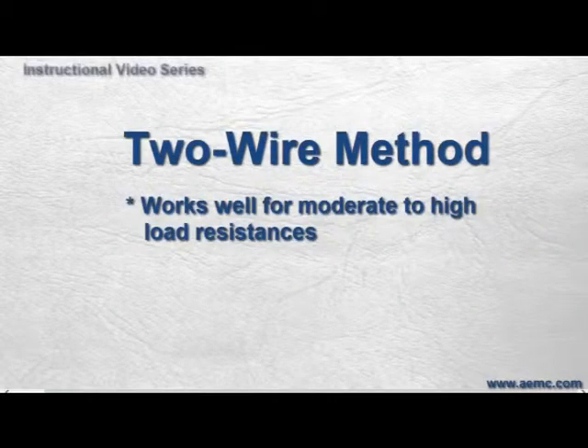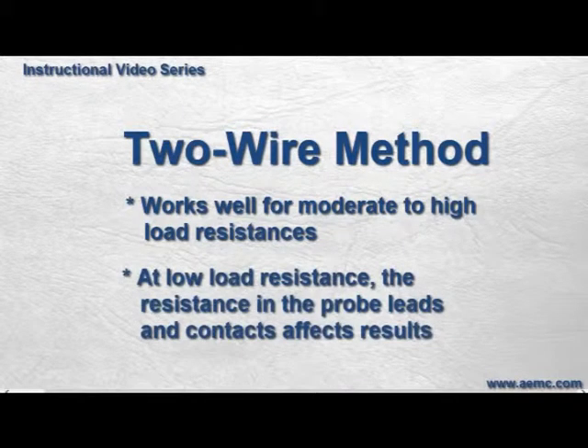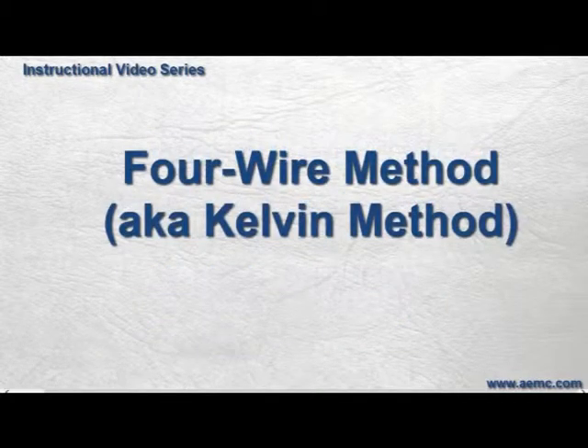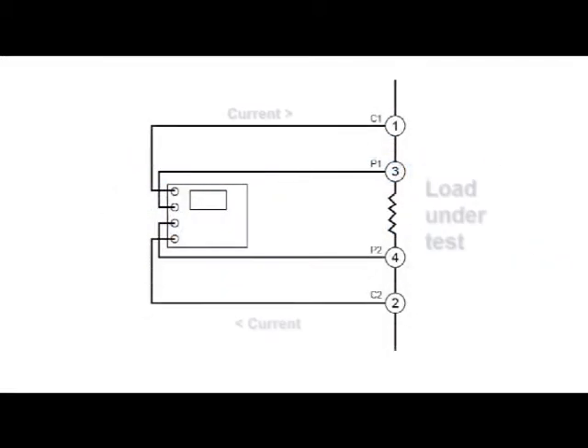The two-wire method works well for moderate to high load resistance or impedance. However, for very low load resistances, the resistance inherent in the probe wiring and contacts can contribute a significant percentage to the overall results, making the measurement of the test load resistance inaccurate. To accommodate this issue, more advanced instruments employ a setup known as the four-wire or Kelvin method. As the name implies, this involves using 4 probes in an arrangement similar to the example shown on the screen.